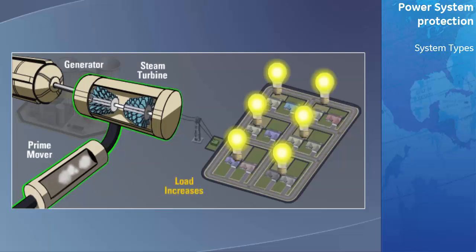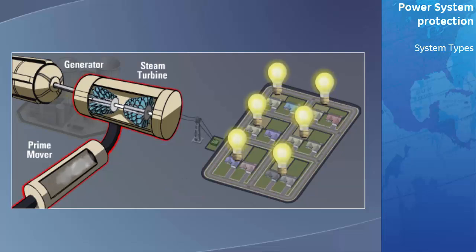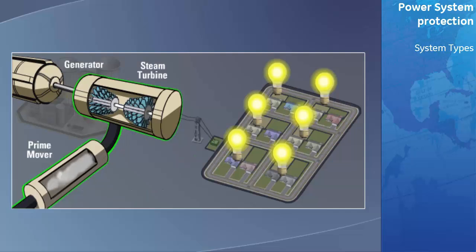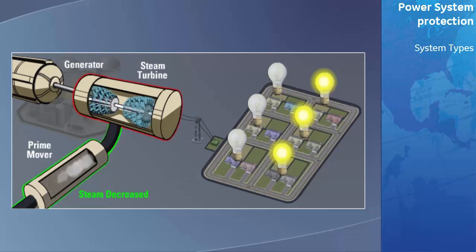As the load increases, the generators would tend to slow down, resulting in a reduction of output voltage and frequency. The generator's control system will sense this and input more mechanical energy to match the increased load. If the demand decreases, the generator will speed up. The control system senses this and then takes appropriate action to reduce the mechanical energy input into the system.